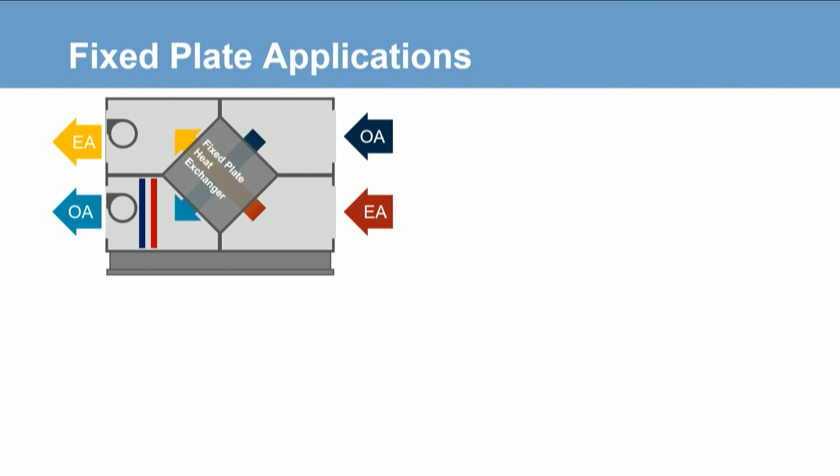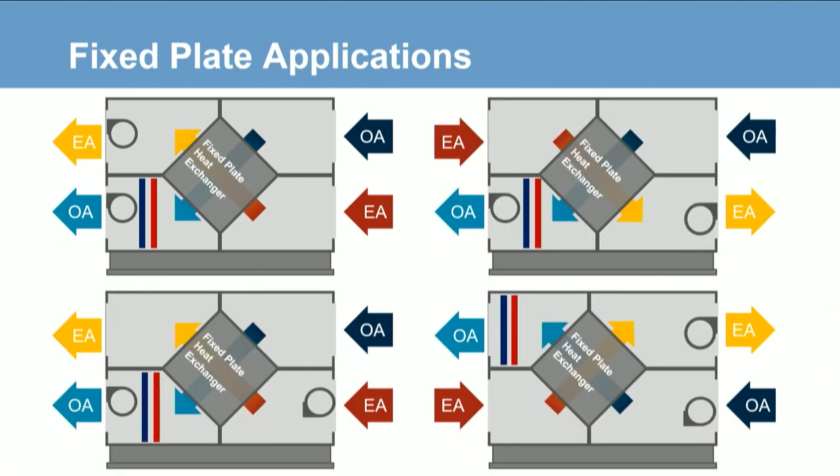Capacity control is handled with face and bypass dampers. Fixed plate heat exchangers can be applied in a variety of ways, though each configuration must be cross flow, allowing some flexibility in fan placement and inlet and outlet locations. In the heating season configuration, outdoor air enters the air handler, absorbs heat as it passes through the heat exchanger and heating coil, and exits. Meanwhile, exhaust air from the building passes through the heat exchanger, releasing heat, and exits the building. There are other ways to lay out components and accomplish the same task.